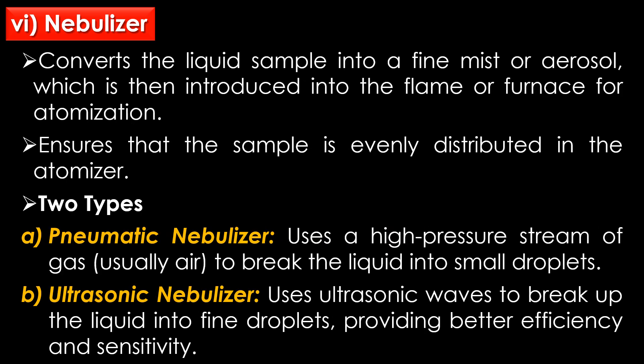The sixth part is the nebulizer, which converts the liquid sample into a fine mist or aerosol that is then introduced into the flame or furnace for atomization. The nebulizer ensures that the sample is evenly distributed in the atomizer. There are two types: the pneumatic nebulizer, which is most commonly used and uses a high-pressure stream of gas to break the liquid into small droplets, and the ultrasonic nebulizer, which uses ultrasonic waves to break up the liquid into fine droplets, providing better efficiency and sensitivity.